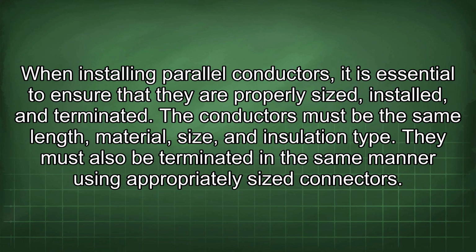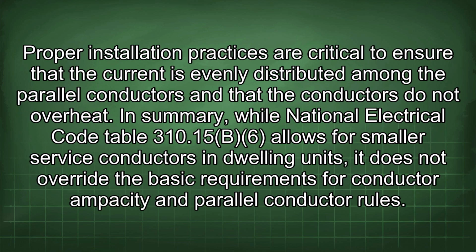The conductors must be the same length, material, size, and insulation type. They must also be terminated in the same manner using appropriately sized connectors. Proper installation practices are critical to ensure that the current is evenly distributed among the parallel conductors and that the conductors do not overheat.